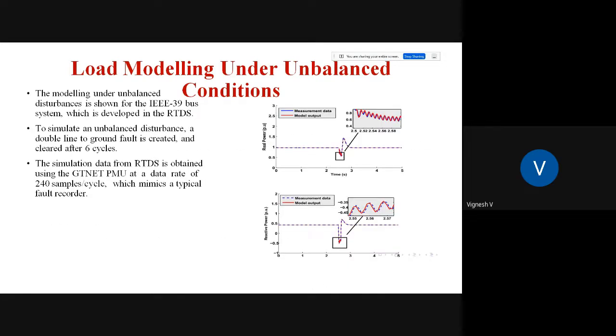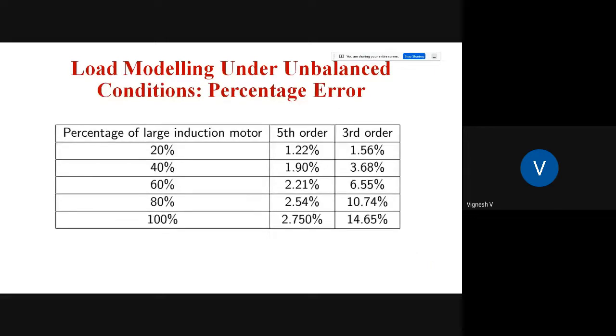So you see that for an unbalanced disturbance, there are double frequency oscillations, because there could be negative sequence components which can have twice the frequency of the positive sequence. So that's why we have this 120 hertz oscillation. This we got from the RTDS. What we did is that we created an unbalanced disturbance, a double line to ground fault, and we cleared it after 6 cycles. You can clearly see that the RTDS data typically gives you the PMU values here. And you can see the double frequency oscillations that arise because of the negative sequence in the unbalanced disturbance. Next slide.